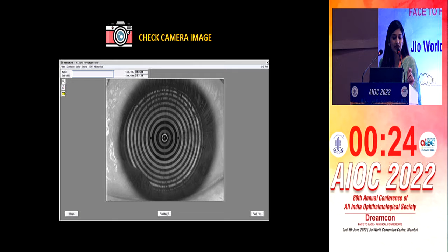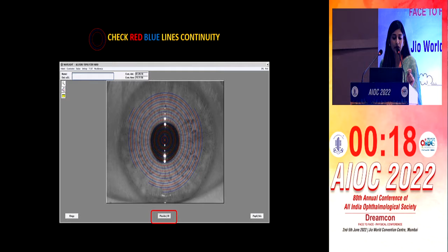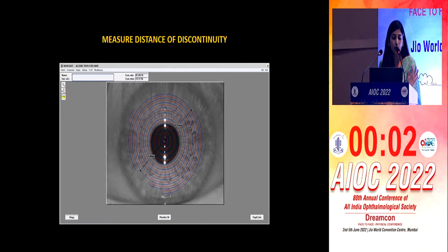We can also assess the quality of the scan by checking the camera image. By clicking on the Placido disc here, we can check for the continuity of the red and blue lines, or the mires. Then we measure the distance at which the first discontinuity of the mires is seen, as you can see here. Normally, we keep an optical zone of around 6 to 6.5 millimeters. So we should make sure that the captured scan here is of good quality, at least in that particular zone, by checking all these parameters.